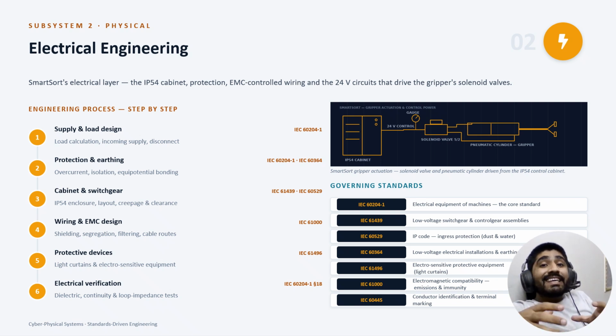Stage number 3, the cabinet itself. IEC 61439 treats the switchgear assembly as a verified product. Temperature rises, short circuit withstands, and clearances are proven, not assumed. And IEC 60529 gives us the IP54 rating. Dust and splash protection, and proof. Chosen for SmartSort's real factory environment, not the brochure photo.